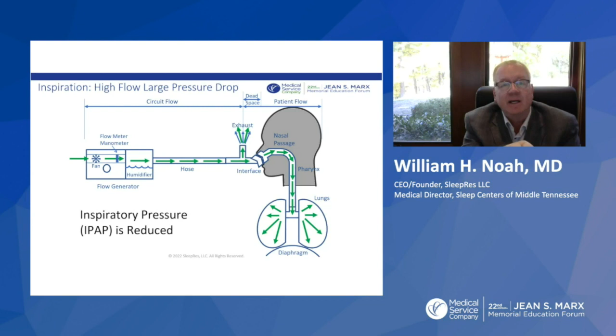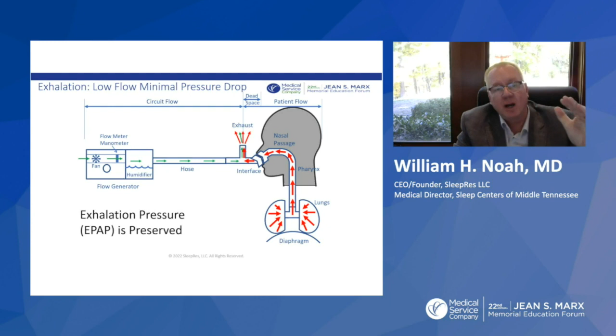But when you're breathing in, now you have the patient flow that's positive, and it's taking the tidal volume in. So you have maximum flow during inspiration, okay? And therefore, as it crosses all these different resistances, the IPAP is reduced. During exhalation, there's no flow going to the patient. The patient's actually exhaling, and there's less exhaust flow because much of the exhaust flow is coming from the patient. So there's very little circuit flow, and therefore very little pressure drop in the system. And in fact, if you're breathing through a nasal pillow mask or a nasal mask where you have to cross the nasal passage, because of the resistance there, you're going to build back pressure. You're going to build EPAP here in the pharynx and in the lungs. So that's why nasal masks require less pressure, and nasal pillow masks require the least. So on inspiration, high flow, big pressure drop. Expiration, low flow, little pressure drop.